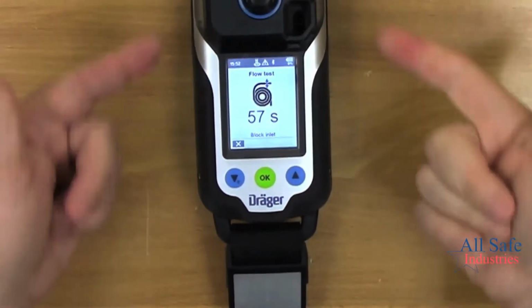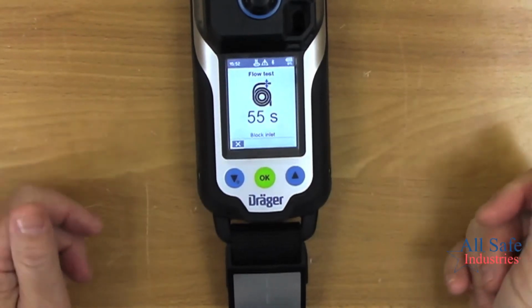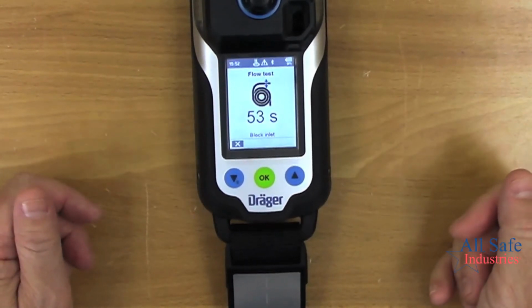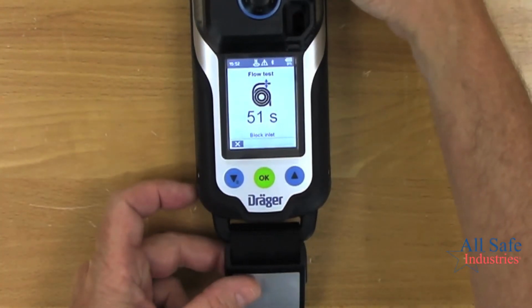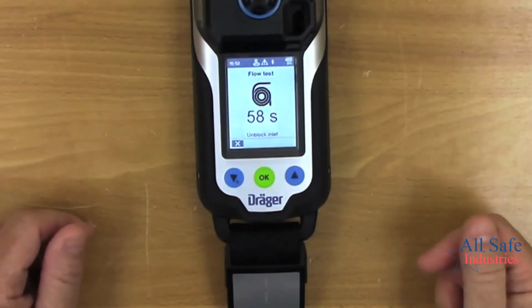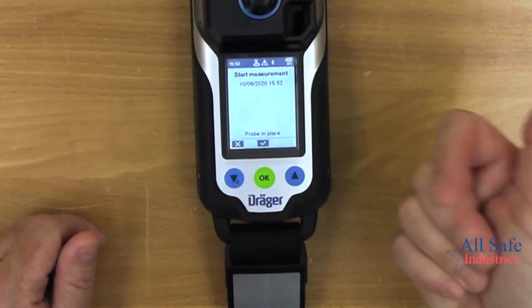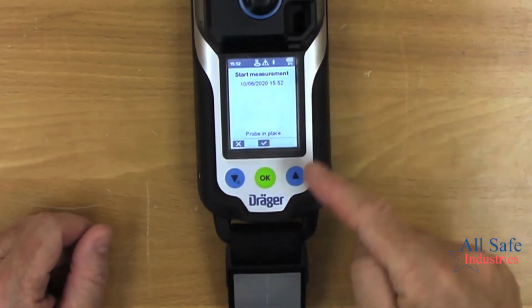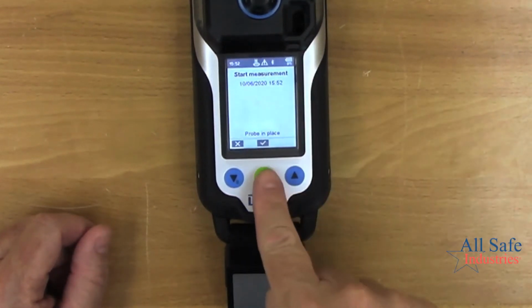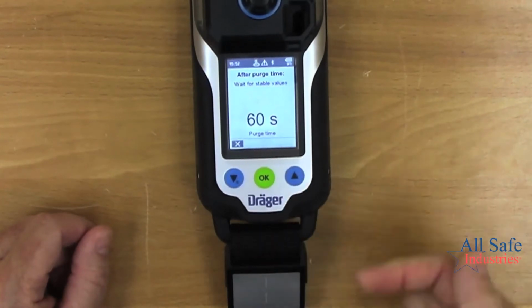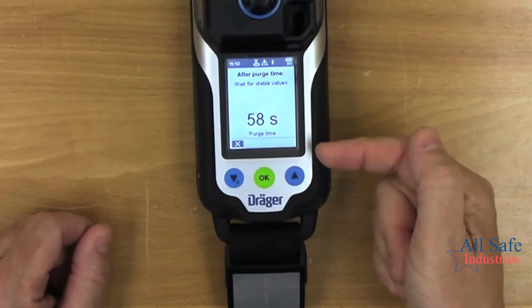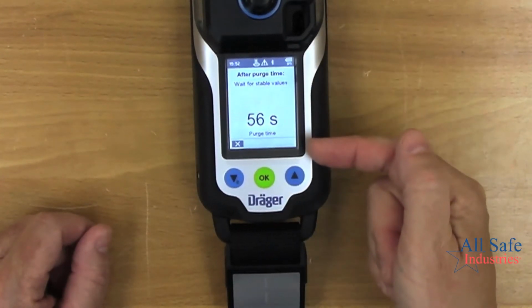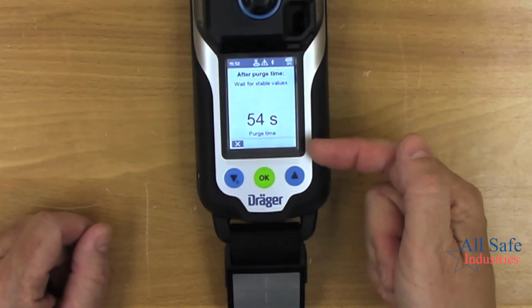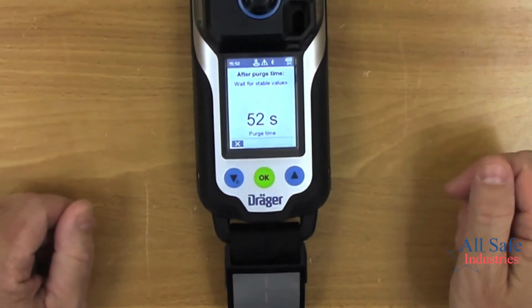As always, when you attach the pump cap, it wants you to do a flow test to make sure the pump is working correctly, so I'm going to block the inlet. That passed, and it told me to unblock the inlet. Hose and probe OK, start measurement. Now it's saying probe in place, so I hit OK, and this gives me a countdown to make sure I'm getting the sample out of the confined space to the sensors in the instrument.